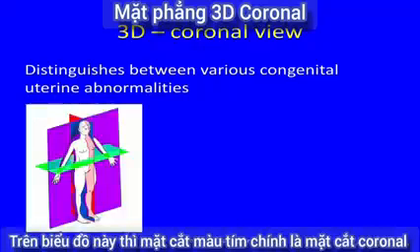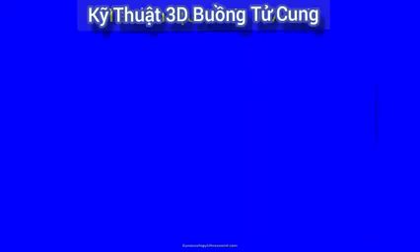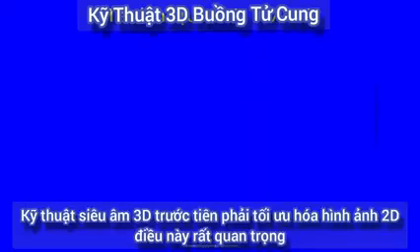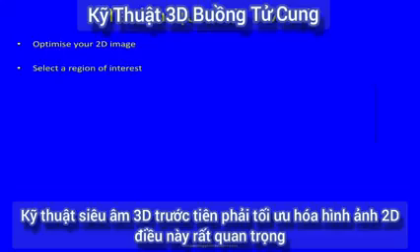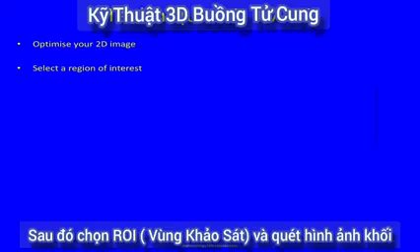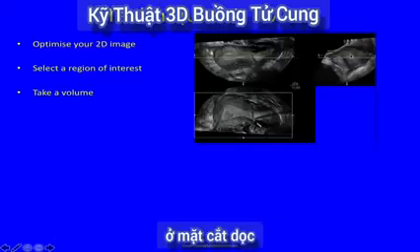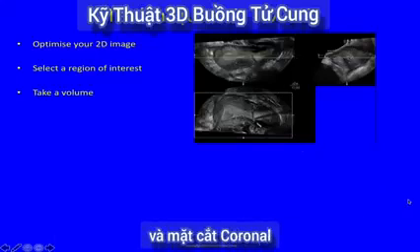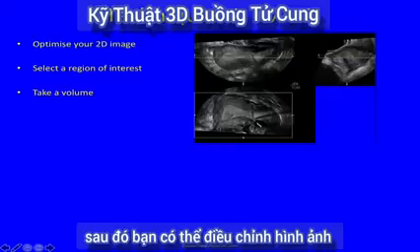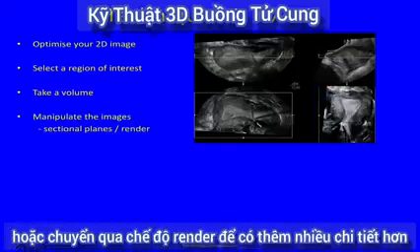In this diagram the plane shown in purple is the coronal plane. The technique of taking a 3D scan is to optimize your 2D image first — this is very important. Then you select a region of interest, take a volume, and that's displayed on your screen in the longitudinal plane, the transverse plane, and the coronal plane. You can then manipulate these images or render it to get more detail.